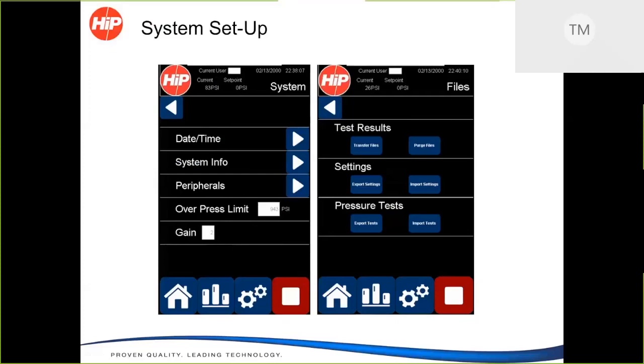In this case, we can monitor that, and we can put a limit on what's a safety overpressure protection that you want. So let's say, again, some of our examples in the past were for 5,000 PSI. Well, in this example, we typed in 943 PSI as an overpressure limit. So what that'll do is if it ever detects that you've gone 943 PSI over your setting, so in the case of those tests we were running before, it would be 5,943 PSI, we'll shut the system down and protect your unit from getting damaged. So think of it as like an overall governor on the amount of pressure that you can generate on your system.